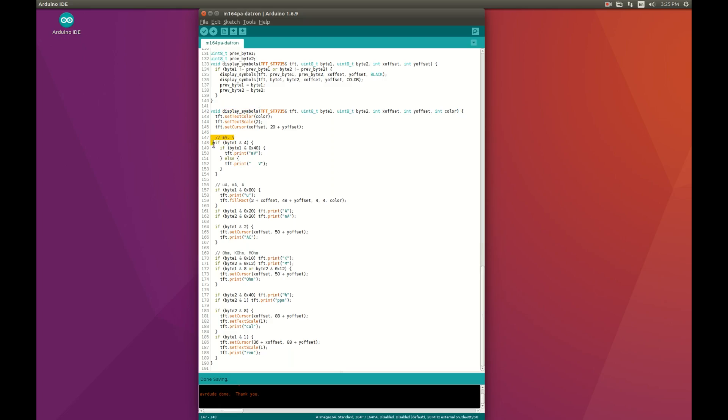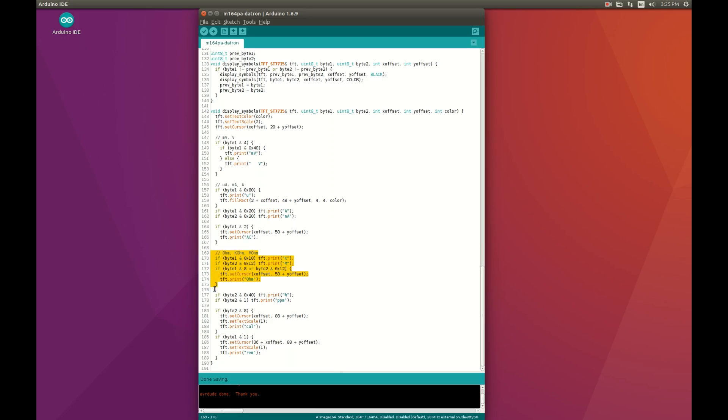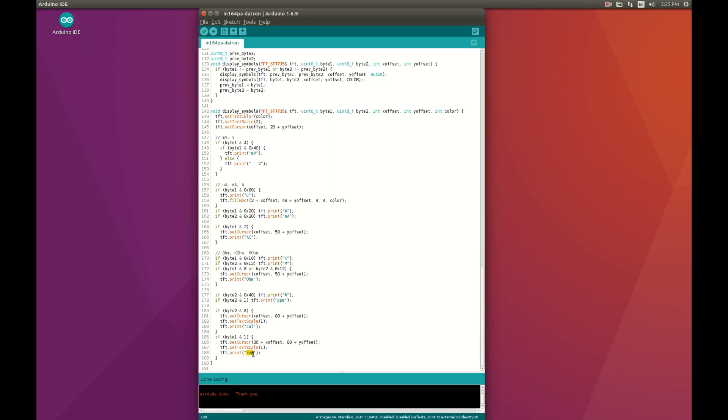And this is to actually print the symbols. This block is to deal with volts. This is to display amps. And this is about ohms. This is about percent. And this is about ppm. And this is for calibration mode. And this finally is for remote operation using GPIB.